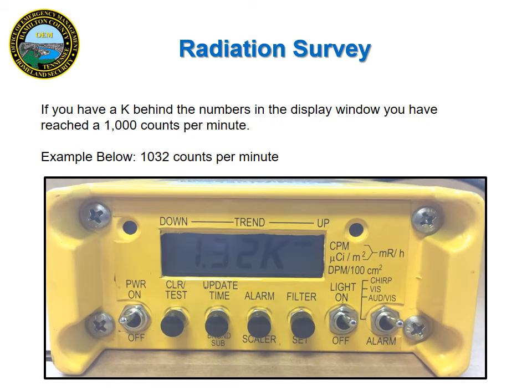On your screen, if a K shows up behind your numbers, you have reached 1,000 counts per minute. So using the example on the screen, the reading is 1,032 counts per minute. Remember, anything over 300 counts per minute is considered contaminated. So if the K shows up, you will have a pretty high level of contamination.